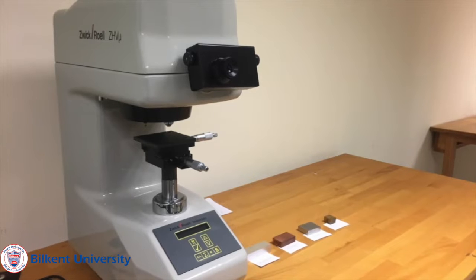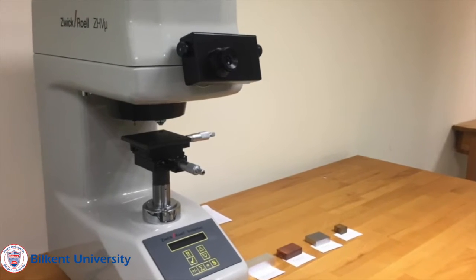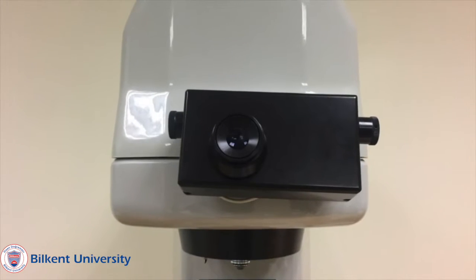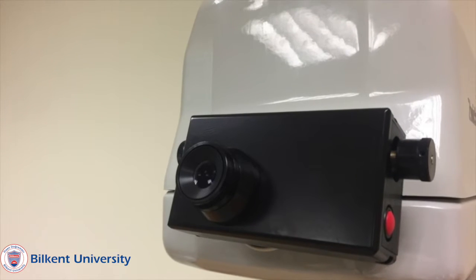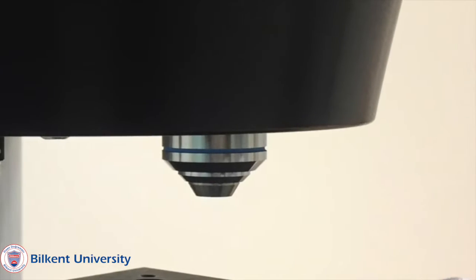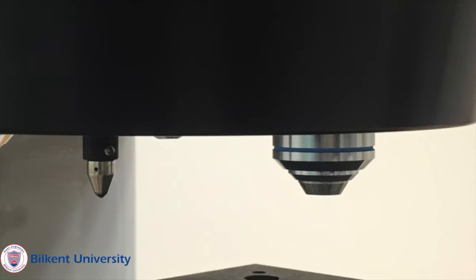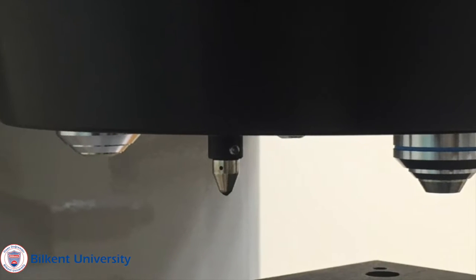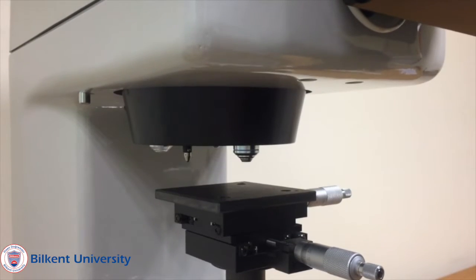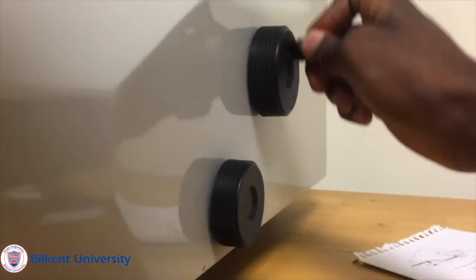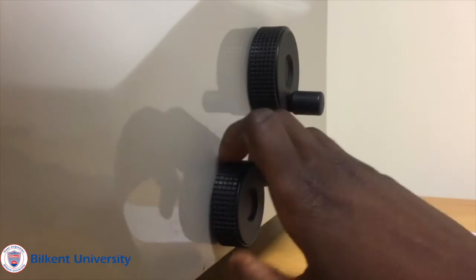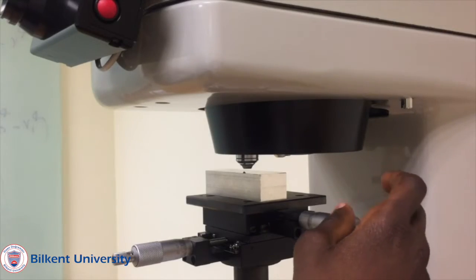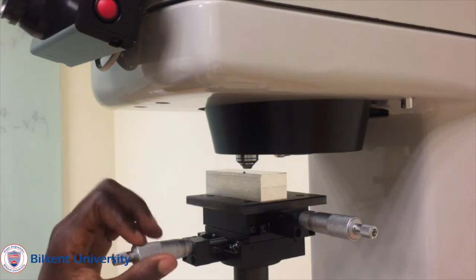We shall be testing using the micro hardness machine, which consists of a viewfinder with a lens and two knobs by the sides, and also a red button which we shall use to record our values. This setup also has a 40 times objective lens, a diamond tip indenter, and a 10 times objective lens. The testing stage could be raised towards and lowered away from the lenses using the two knobs by the sides of the machine, and could also be moved laterally in both directions using the screw gauges just below the stage.